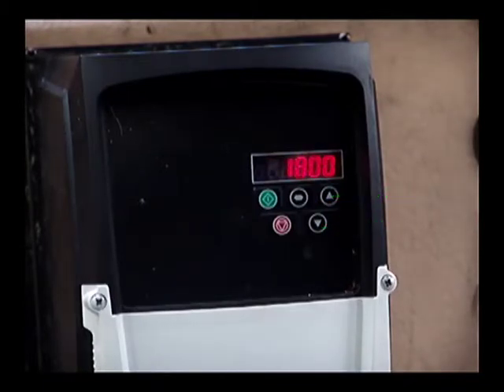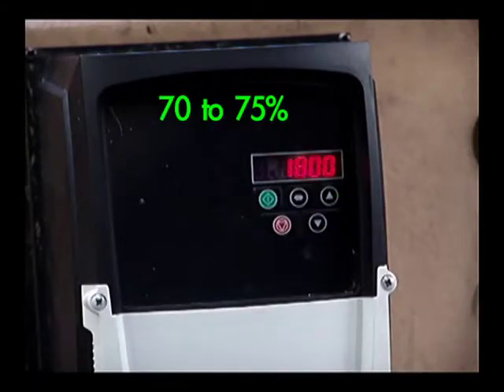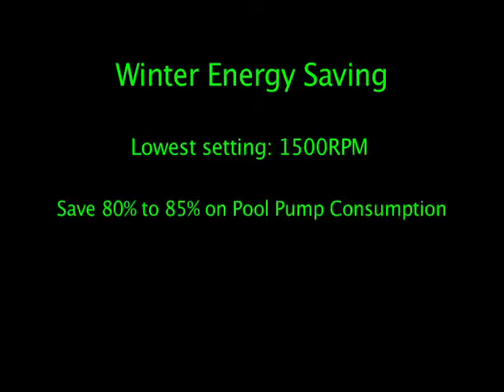Now we find that at 1800 RPM, you can achieve savings of 70 to 75% depending on the size of the motor. In winter, greater energy savings can be achieved by setting your motor down to the lowest setting of 1500 RPM. You can achieve 80 to 85% saving on your pool pump's consumption. And with the growing electricity prices, why wouldn't you want one?